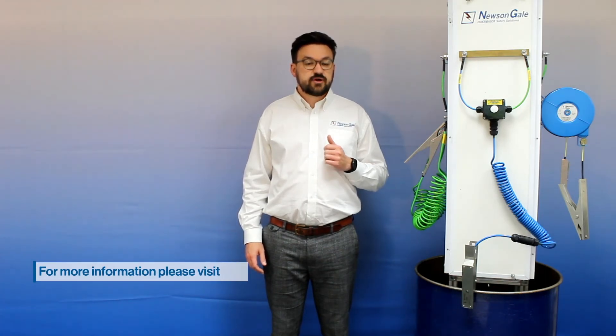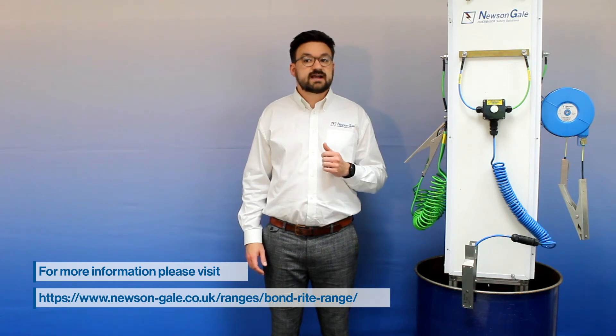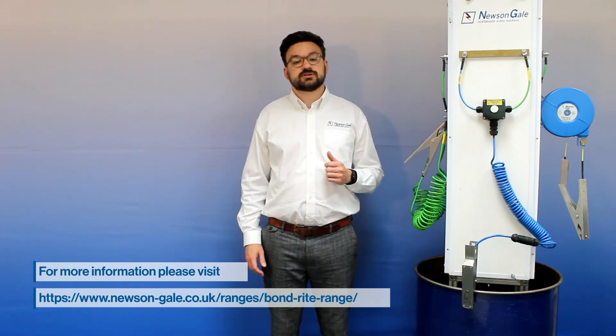All Bond-Rite units supplied with a battery are powered by an intrinsically safe 9 volt lithium battery that powers the unit for up to six months for equipment grounded six hours a day. If process applications require grounding for longer, we recommend our mains-powered option, the Bond-Rite remote EP.